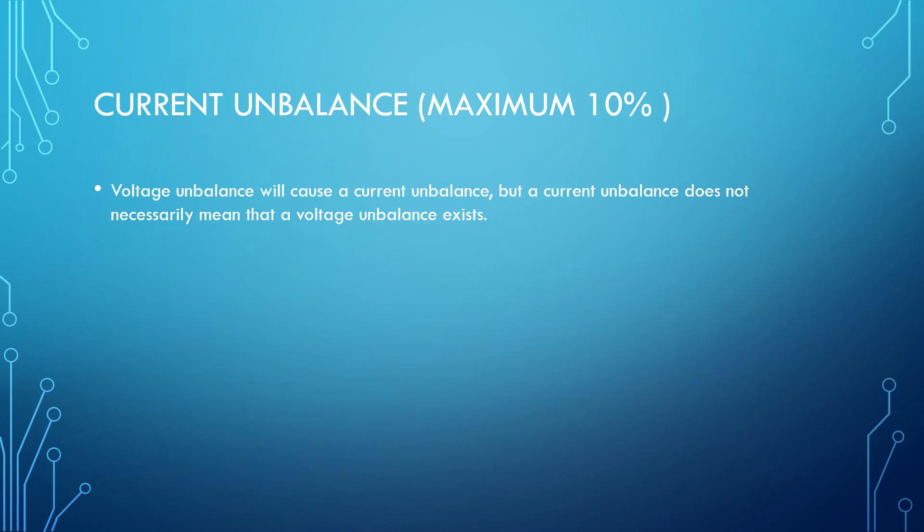Current unbalance is allowed to a maximum of 10%. Voltage unbalance will cause a current unbalance, but a current unbalance does not necessarily mean that a voltage unbalance exists.